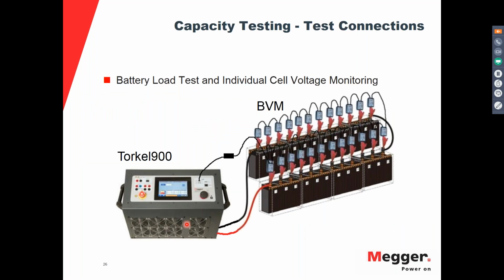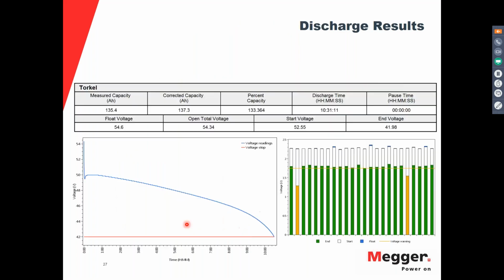The connection of a load bank depends on what load bank you have. Here, this slide is showing our Torkel 900, which is the load bank that we offer for this type of test. It is also showing the connection of individual cell voltage monitoring. This will monitor the voltage of each cell throughout the test, on top of the overall voltage that the Torkel is monitoring. So it's a simple connection, and you get a lot of information from this kind of setup.